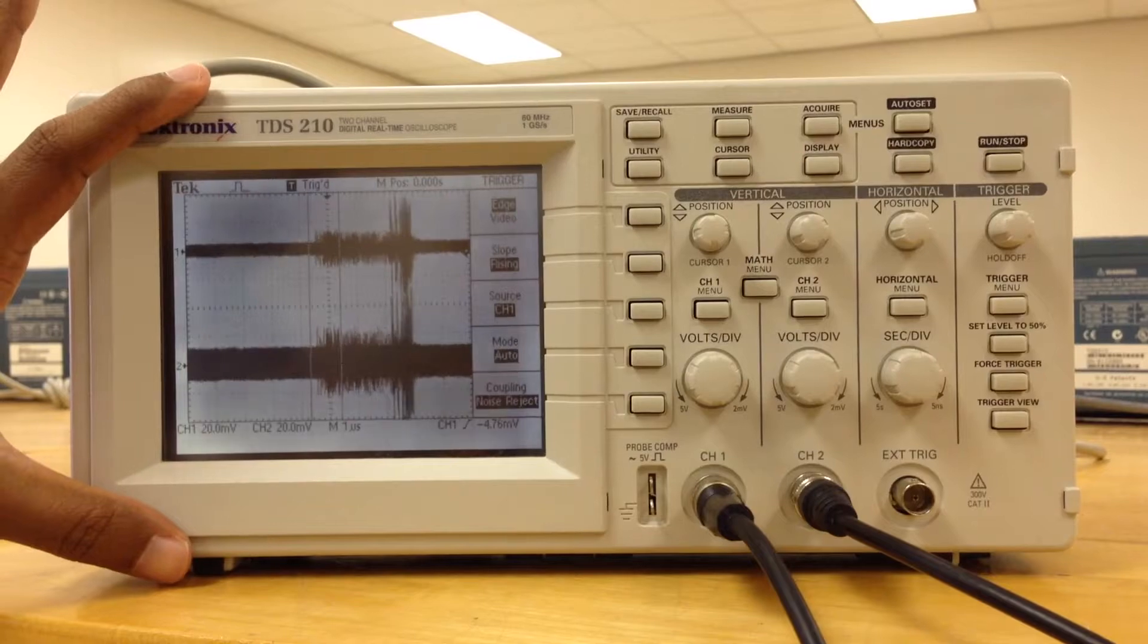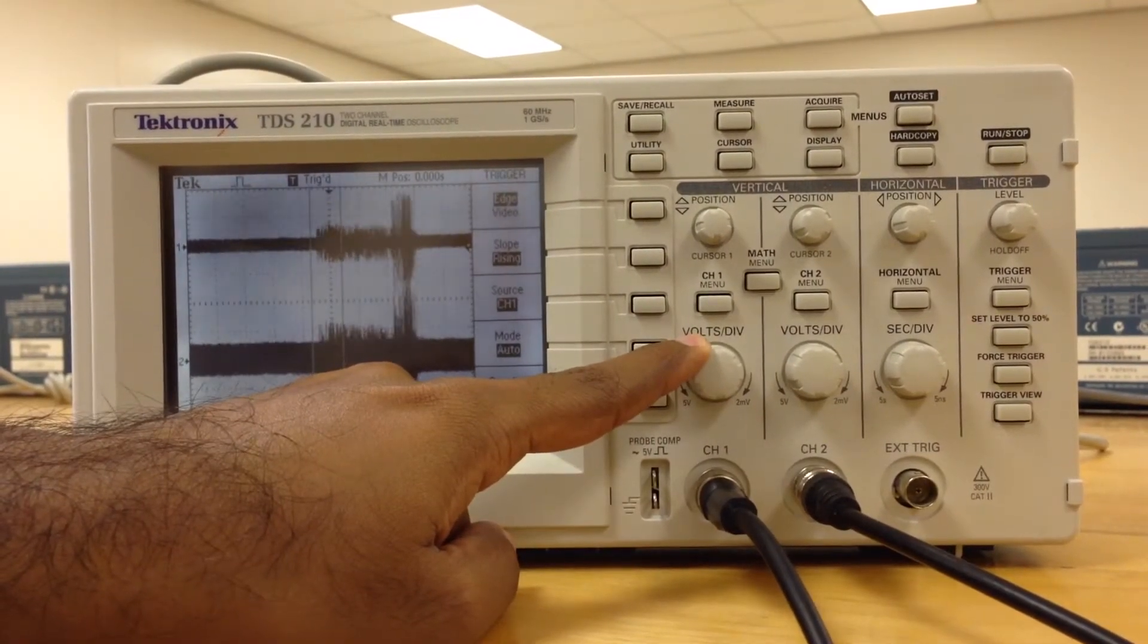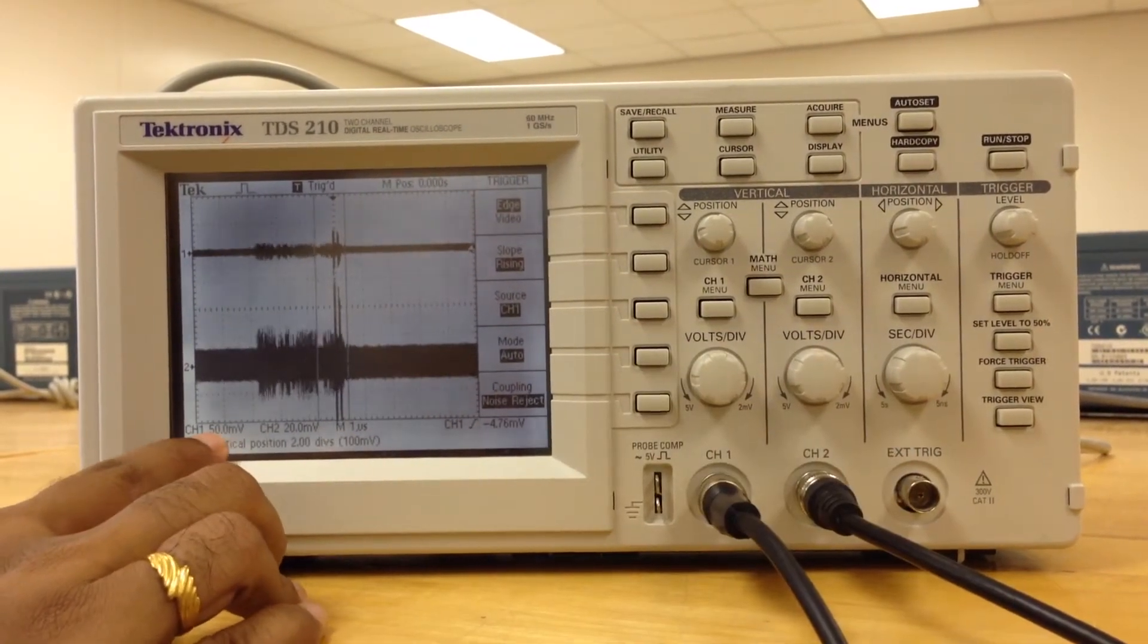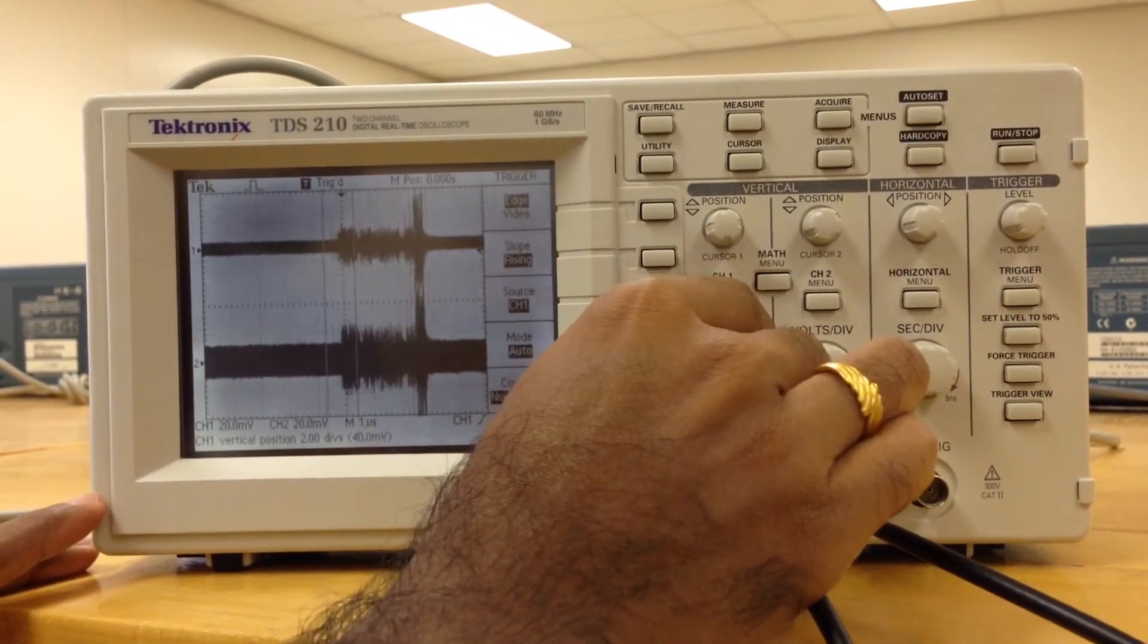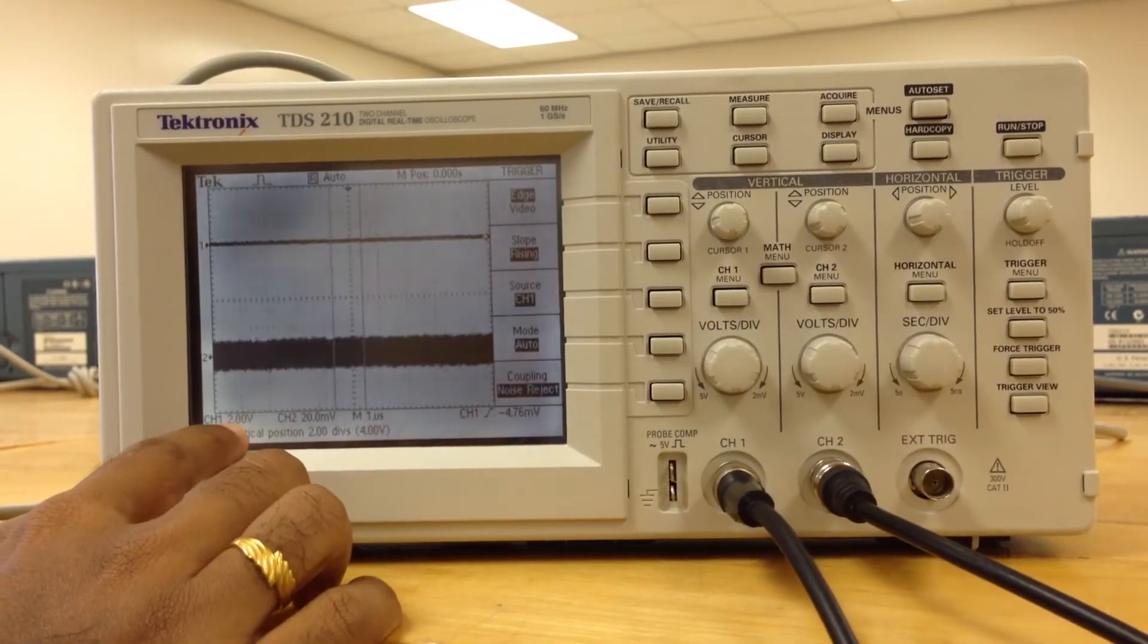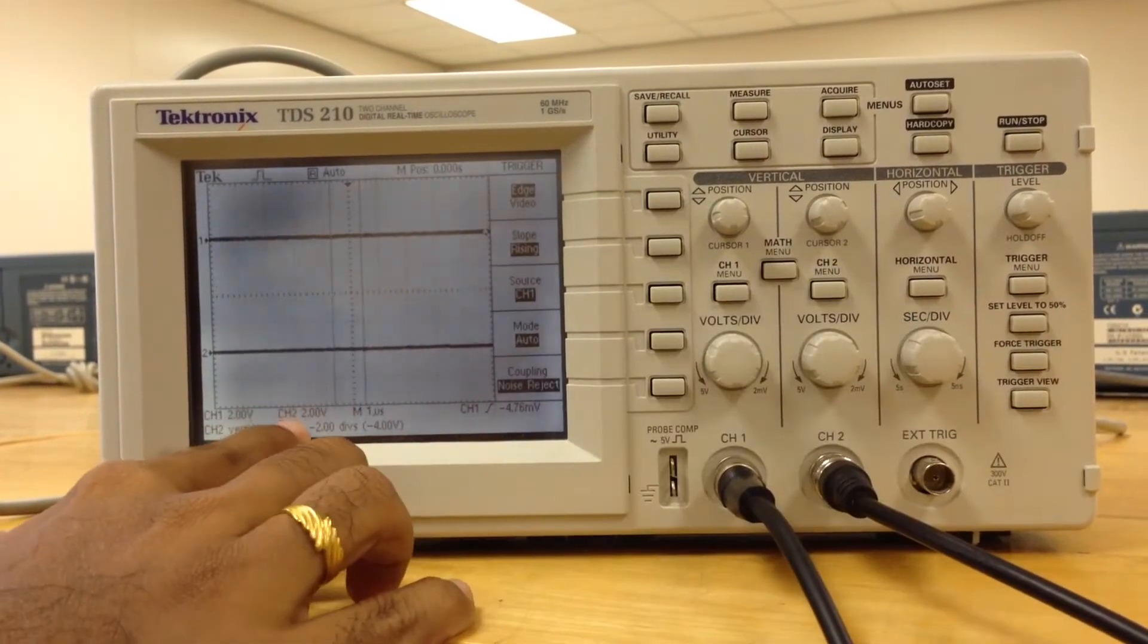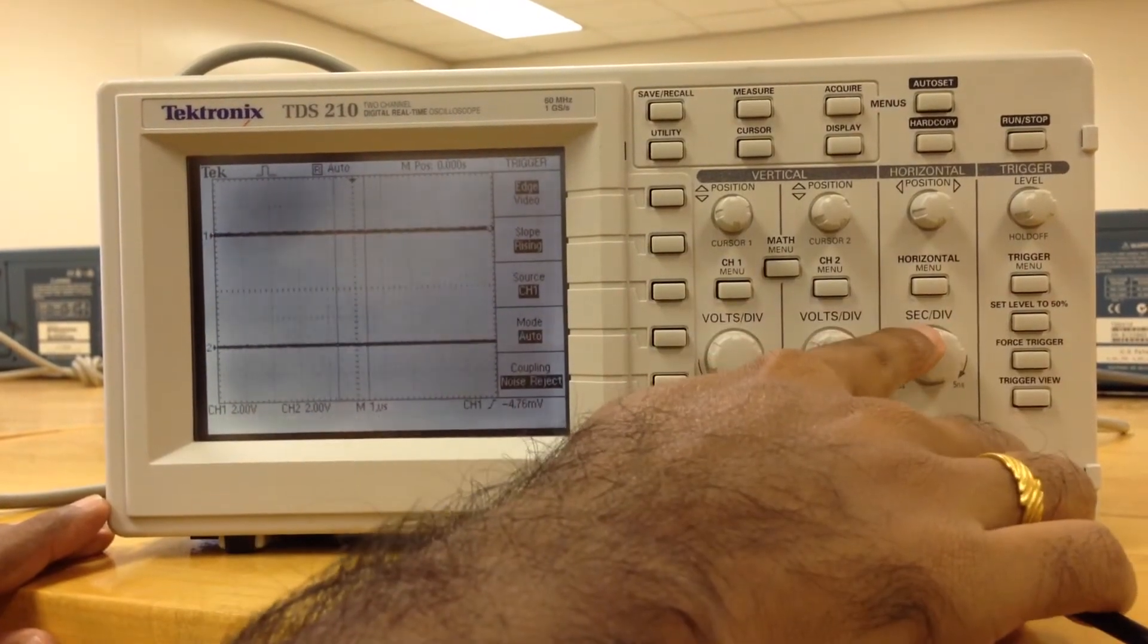Now adjust this vertical section, volts per division. As you adjust, make sure we get 2 volts. I'm adjusting this, now it shows 2 volts. Do the same for channel 2. As you can see, this shows 2 volts. Now adjust this seconds per division.